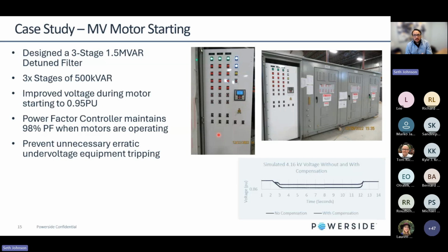And this brought a lot of value to the client because we're preventing unnecessary and erratic undervoltage equipment tripping that was happening throughout the facility. And this wasn't limited to just the 5 kV bus. This was happening in other locations throughout the facility. So we were able to get this from a 12% voltage sag to 5% with this solution. We could have even gone a bit further if needed, but it certainly wasn't a requirement for this application.